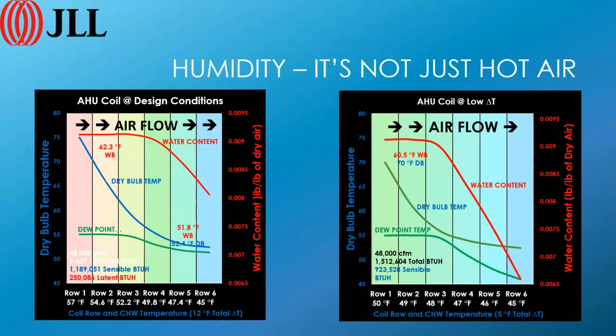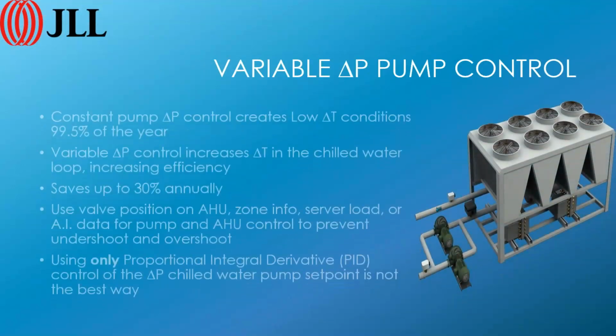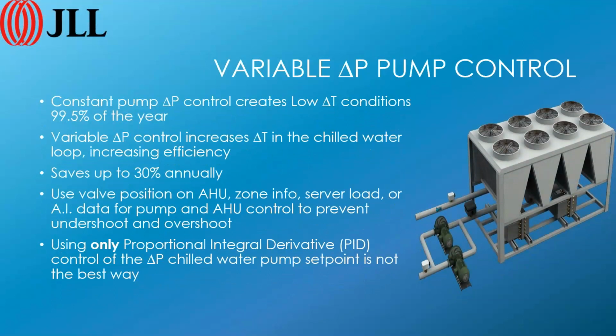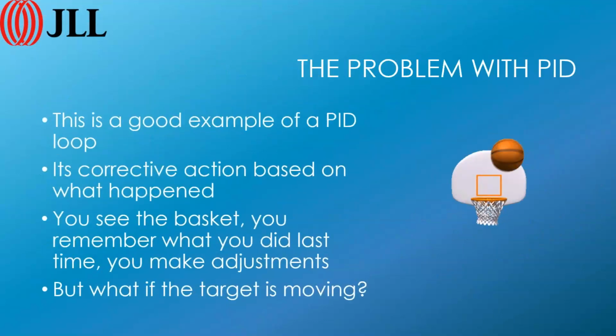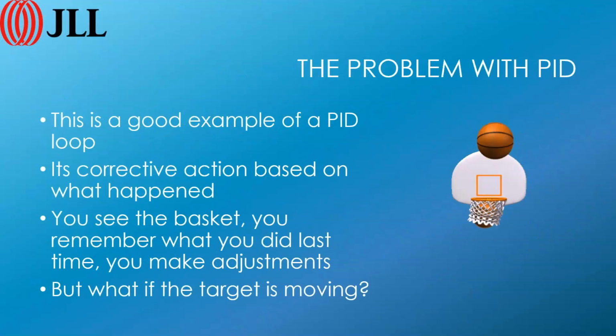Okay, when resetting condenser water temperature, I think you said you do it based on plant kilowatts. How does that account for changes in the plant load? In other words, if the plant kilowatts increase, it could be because the change to condenser water temperature was not helpful, or because the load itself increased, right? Correct. Yeah, that is correct.